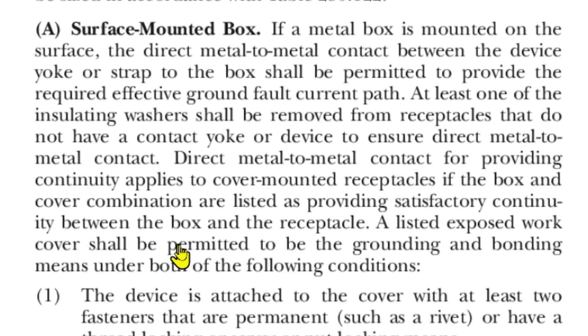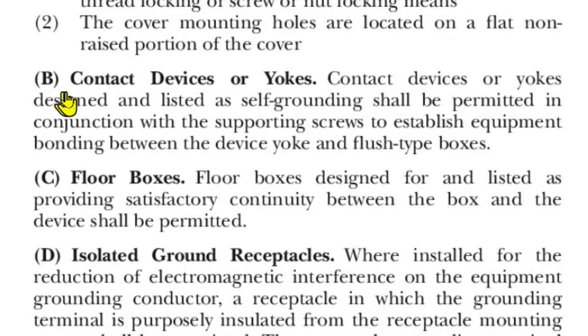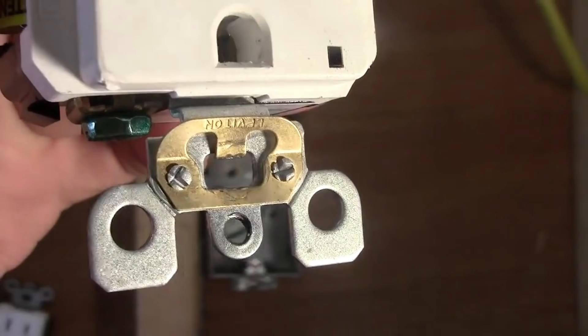And here we have B - contact devices or yokes designed and listed as self-grounding shall be permitted in conjunction with the supporting screws to establish equipment bonding between the device yoke and flush type boxes. So the devices must be designed and listed as self-grounding, and the ones I showed you with the self-grounding clips are.